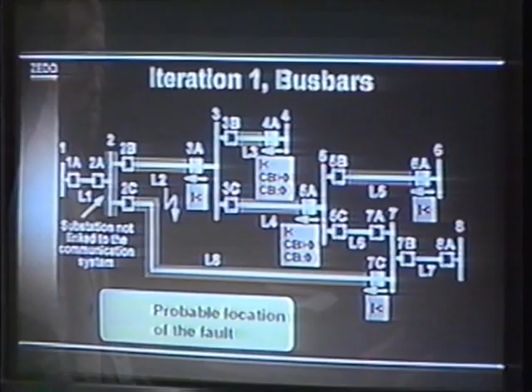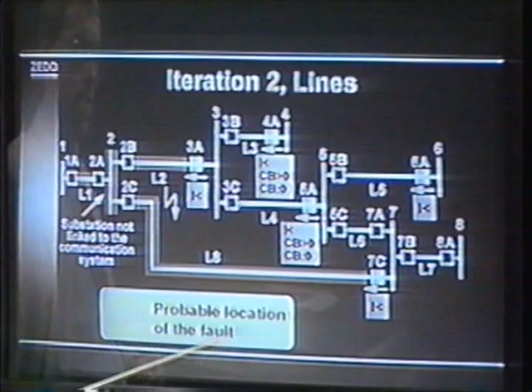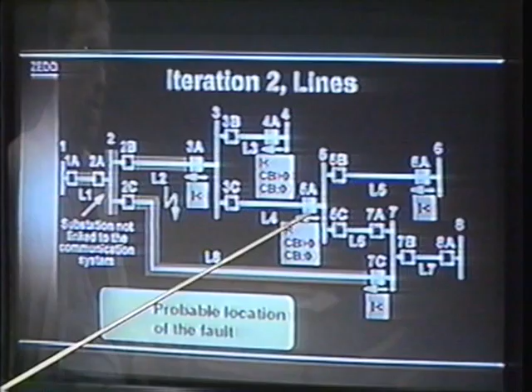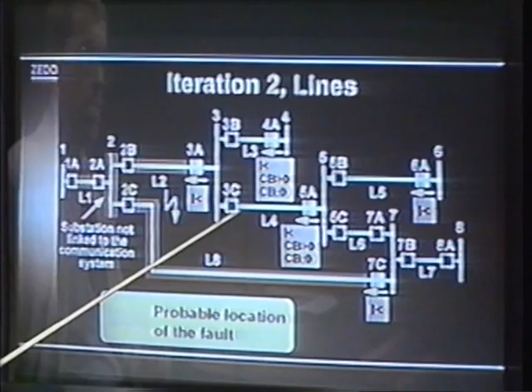In the first part of the second iteration, the device-specific artificial neural networks doing the diagnosing process for lines are applied. We can see that, for example, line L5 is no longer called part of the probable location of the fault, because the intermediate diagnosis generated for busbar 5 is that the fault is on line L4 or even further to the left side. This intermediate diagnosis is provided to the DSANN doing the diagnosis for line L5, and the result is that the line isn't called part of the probable location of the fault anymore. In the same way, the first intermediate diagnosis has been reversed, so lines L3 and L4 are not called part of the probable location of the fault anymore.